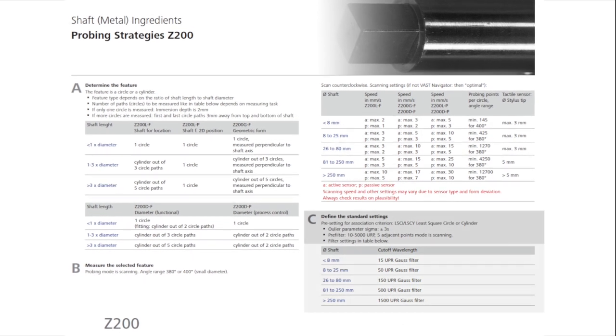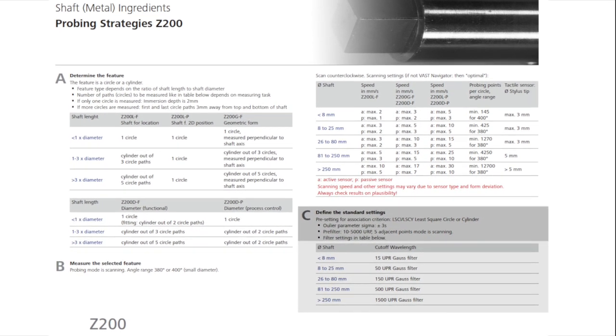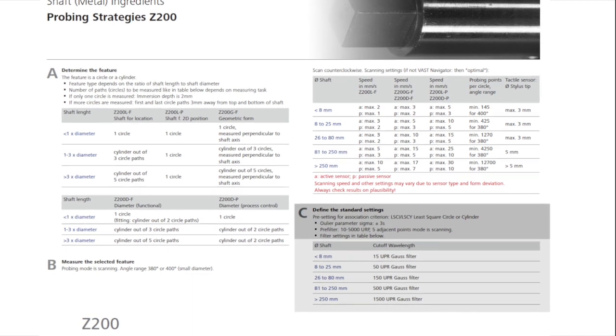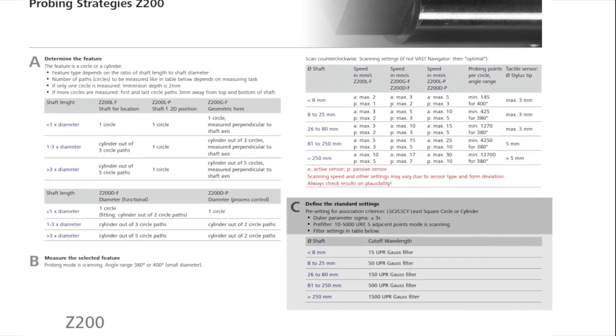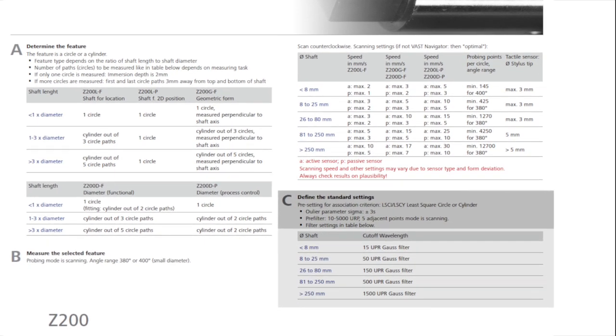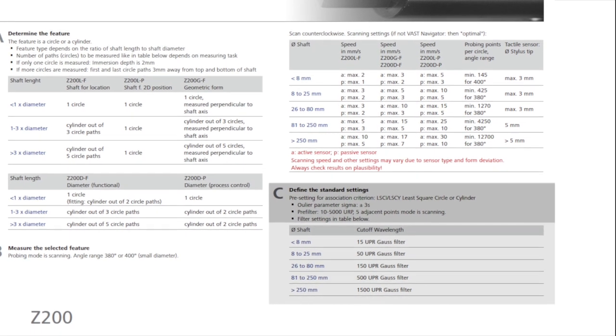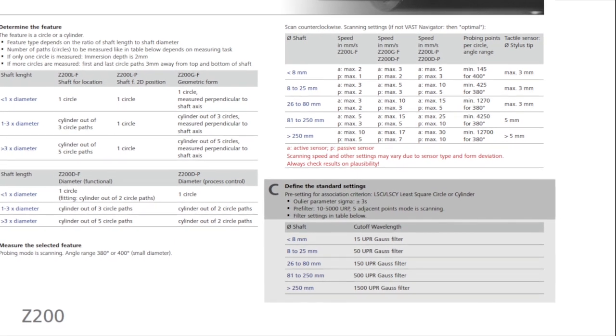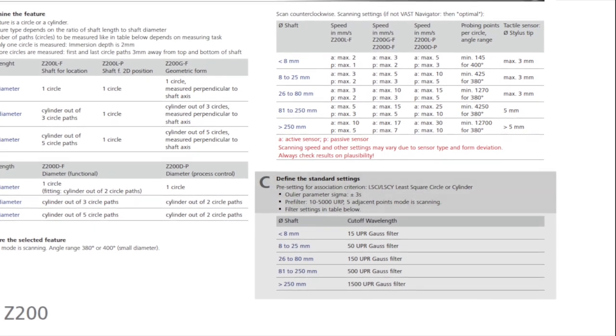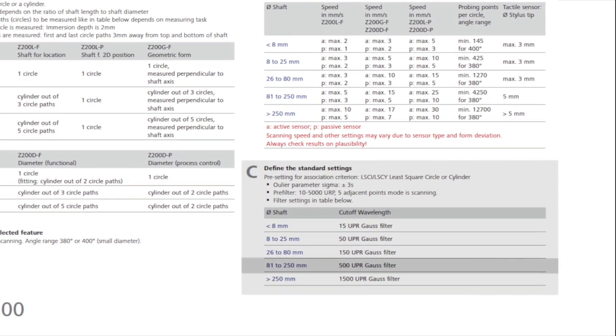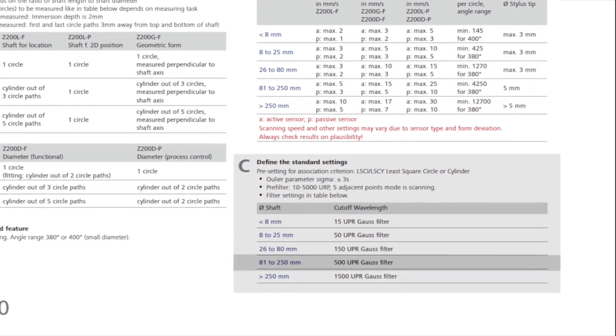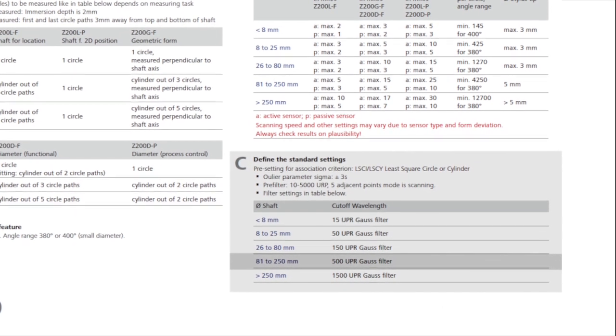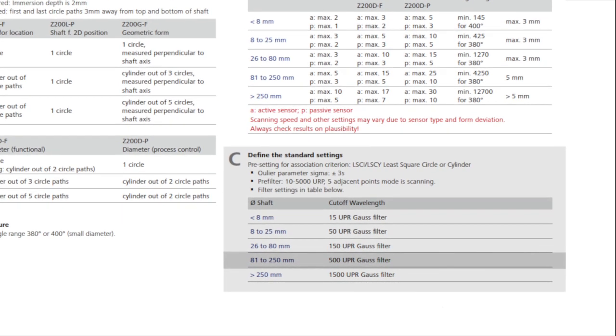Additionally, the circle should be evaluated with outlier elimination, setting the parameters of sigma at plus or minus 3, and with 5 adjacent points, and pre-filtering at 10 to 5,000 undulations per revolution. The measured circle is then evaluated by a Gauss filter, with a cutoff frequency of 500 undulations per revolution.